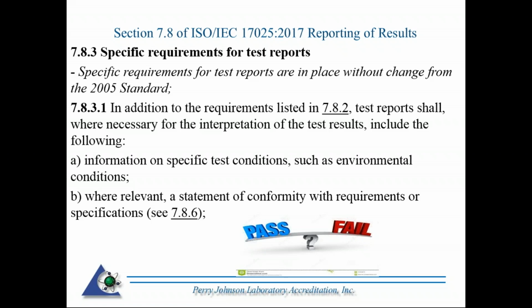Where relevant, a statement of conformity with requirements or specifications. If you're stating a statement of conformity, we're going to expand on that a little bit here because there's a whole new section in the standard just dealing with that. Well, I've got pass/fail written. That's an example of when you make a statement of conformity. It could be pass, fail, in tolerance, out of tolerance, any wording like that is making a statement of conformity.